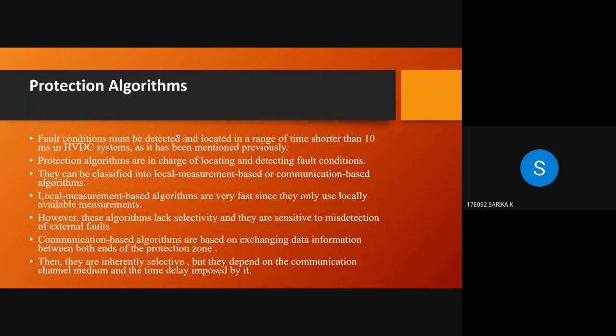Now let us see about protection algorithms. Fault conditions must be detected and located in a range of time shorter than 10 milliseconds in HVDC systems, as it has been mentioned previously. Protection algorithms are in charge of locating and detecting fault conditions. They can be classified into local measurement based or communication based algorithms.